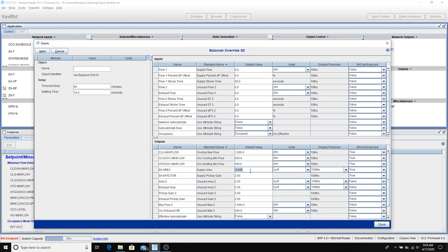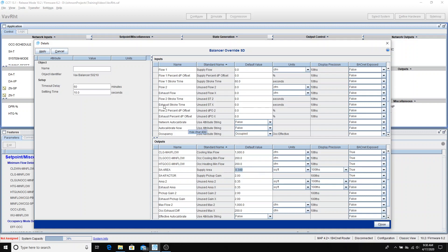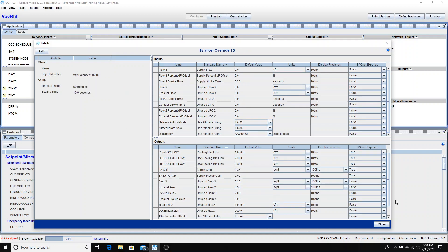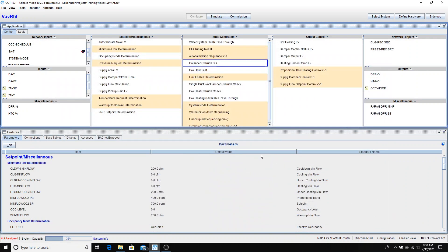And then, last but not least, the SA area. That's the size of the box in square feet. So if you know the radius of the box, if it's a round box, then if you want to do the math on it, it is pi r squared. So you would take pi times the radius squared, that would give you the size in square inches. And then if you divide that number by 144, that gives you square feet. So you don't have a chart that tells you what those sizes are. So we'll apply those changes. Go to Close.